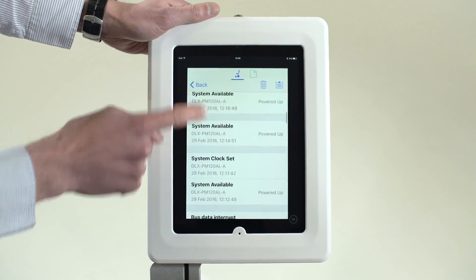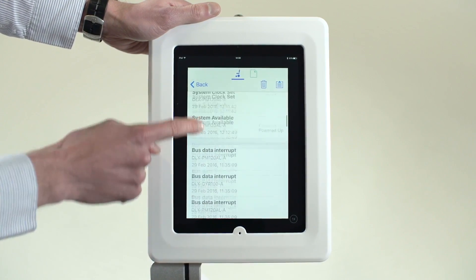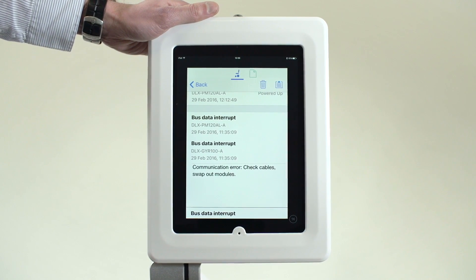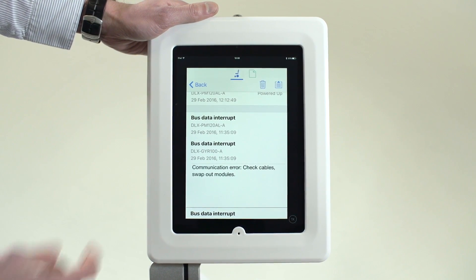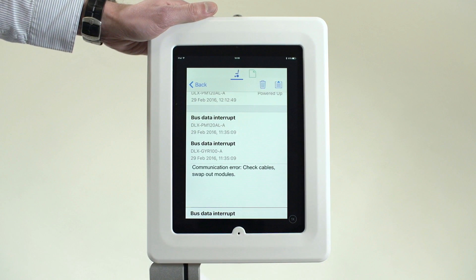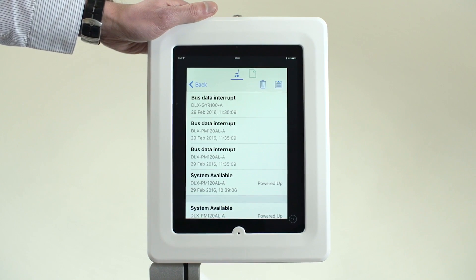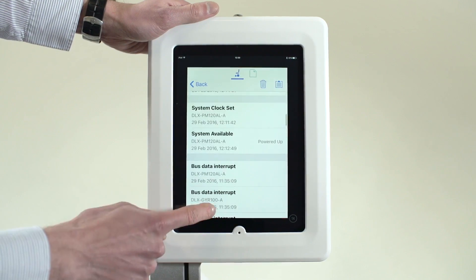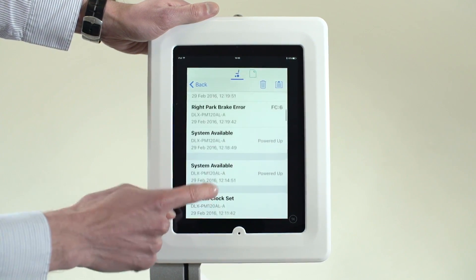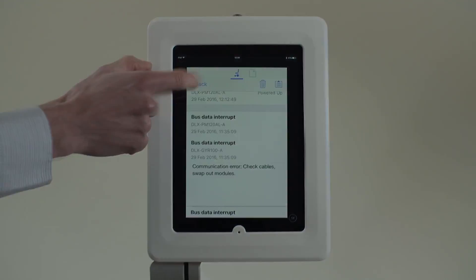It is now possible to see how often the event is occurring and also when, to potentially help understand the cause. For example, is it happening once a week at a set time? The error could be as a result of a specific action or situation. Events are also logged and displayed here, such as when the system is powered up, shown as system available. Tap Back to exit.